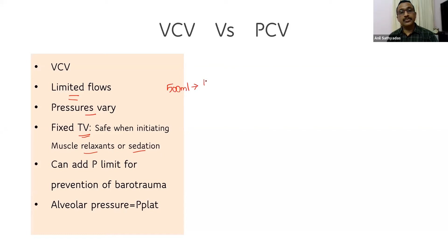pressure limit. So when the ventilator reaches that pressure in volume control mode of ventilation, it will know that it should not exceed that pressure. The normal default setting for pressure limit is 40 centimeters of water. So when you connect this patient to the ventilator, if your target tidal volume is 500 ml and the pressure needed to deliver 500 ml is less than 40, the ventilator will deliver 500 ml.